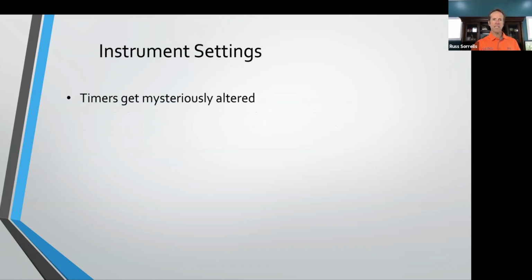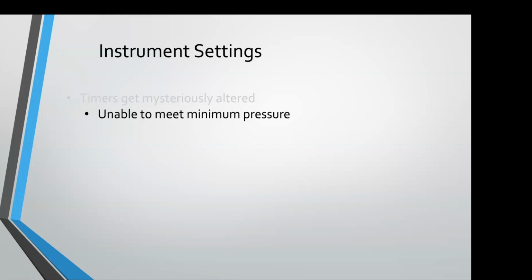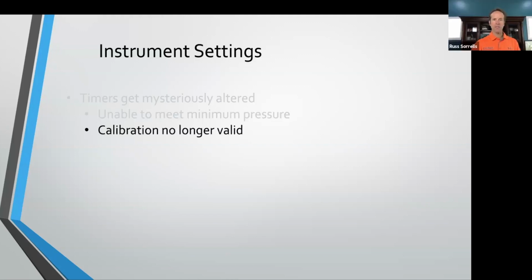Let's talk about instrument settings right quick. Timers get mysteriously altered. Your operators make some adjustments, and you didn't know about it. Nowadays, of course, instruments can be locked out at any number of levels, but we've seen that. I've seen that lots and lots of times because, as a general rule, people want it to run faster, and we get that. But the problem is when you change the timers, you've voided your calibration, right? Yep. So when people change timers, you're unable to meet your minimum pressure. Your calibration, like I mentioned there, is no longer valid.